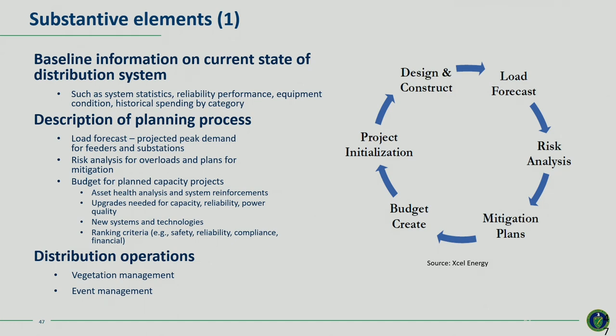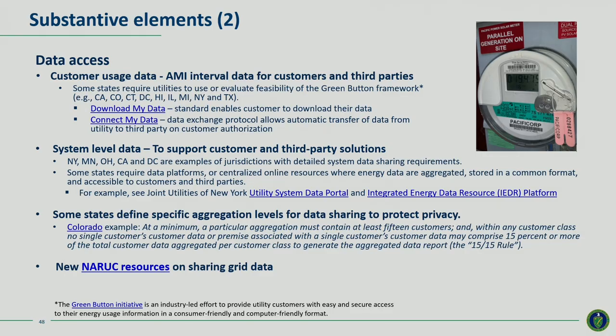Distribution operations are also really important, and you want to see information in the distribution plan around vegetation management — so important given all the wildfires we've been dealing with — as well as managing reliability events: what is the utility doing to prevent outages, and when outages do happen, how do they get back online as quickly as possible? On data access, there are two kinds: customer usage data using interval information from advanced metering infrastructure, and system-level data on things like solar hosting capacity and interconnection queues. New York and California require online data platforms — a standardized way to show information to developers, customers, and third-party service providers in a common format. States are also establishing aggregation requirements to ensure customer privacy; for example, Colorado has a 15-15 rule requiring shared data to represent at least 15 customers with no single customer representing more than 15% of the aggregated data.